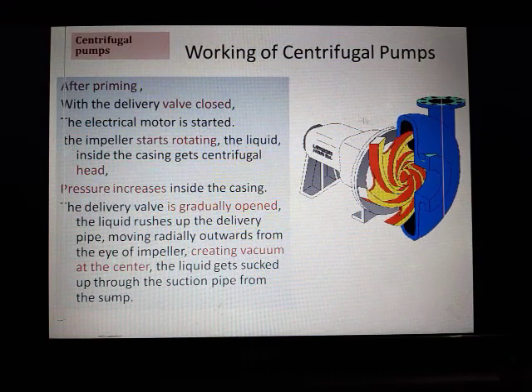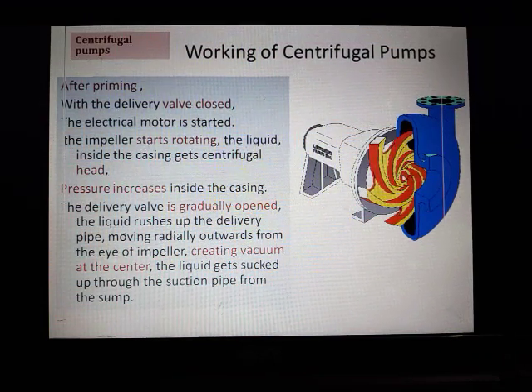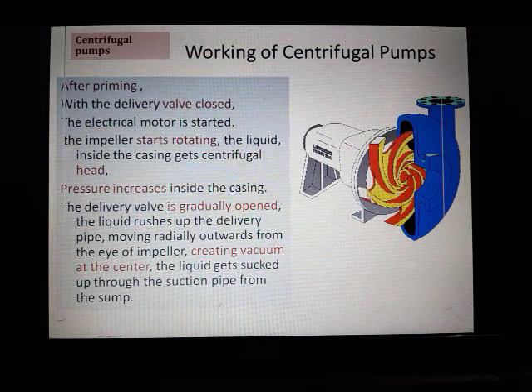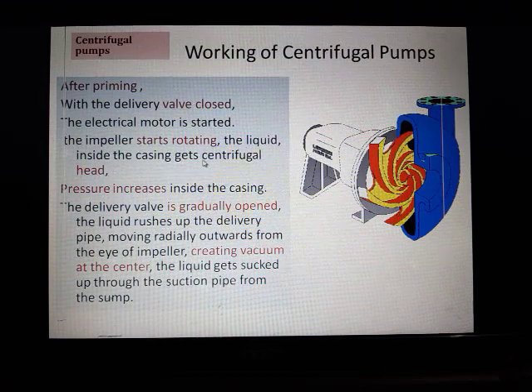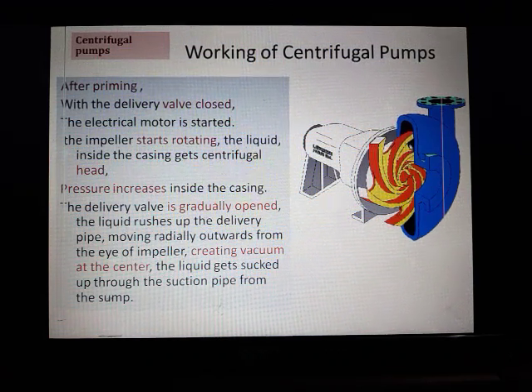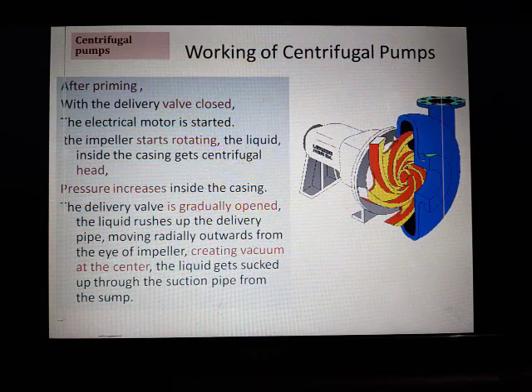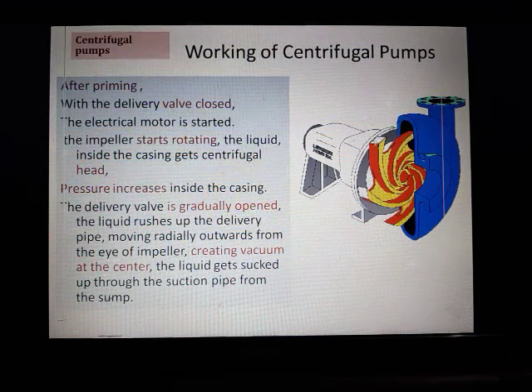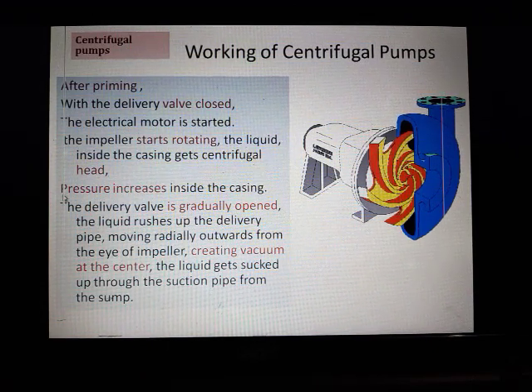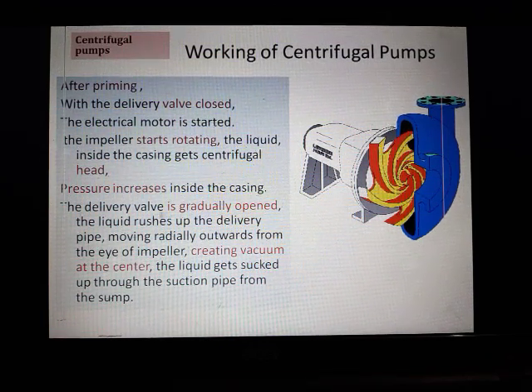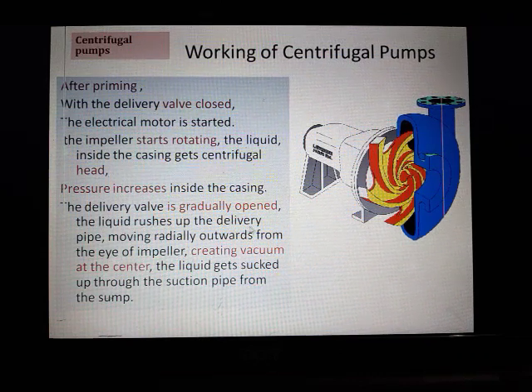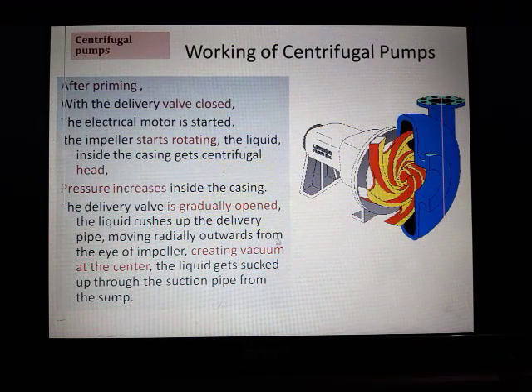After starting the electrical motor, the shaft connected to the impeller causes the impeller to start rotating — in this case in an anticlockwise direction. The liquid inside the casing gets centrifugal head. Since all the space is filled with liquid due to priming, when it rotates the water gains energy and tries to move radially outward at the edges. Pressure is developed at the periphery, the delivery valve is gradually opened, and the liquid rushes up the delivery pipe, moving radially outwards from the eye of the impeller.